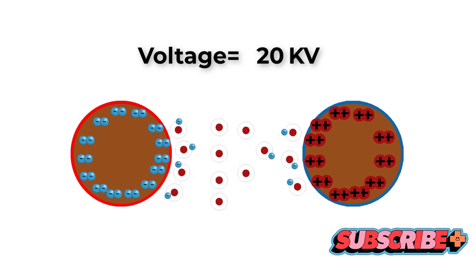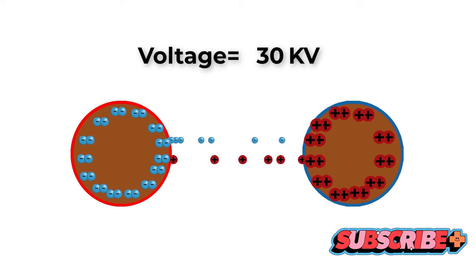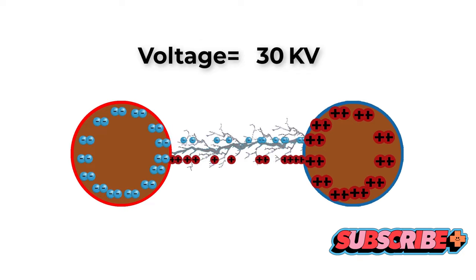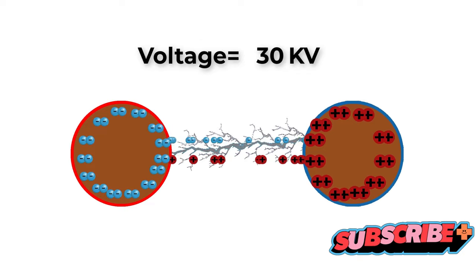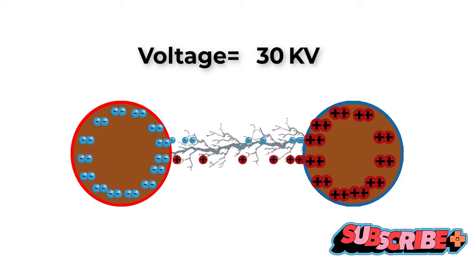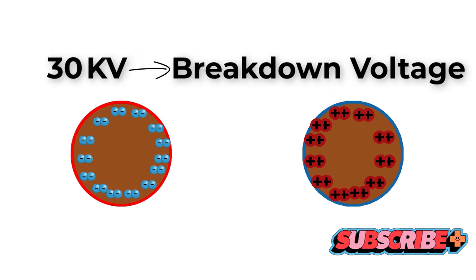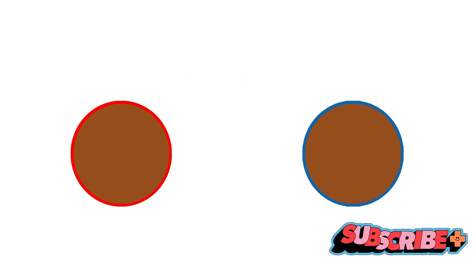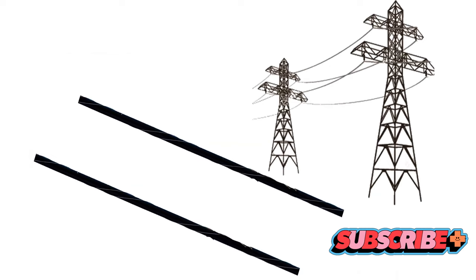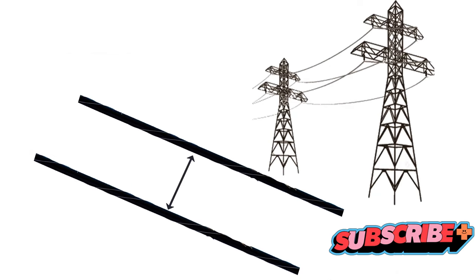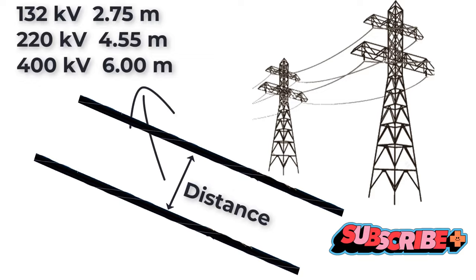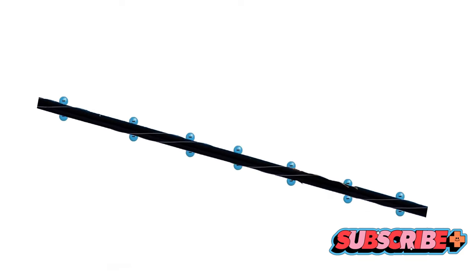Corona discharge is primarily caused by the ionization of air near conductors when the electric field strength surpasses a critical value. When the electric field gets too strong, it can rip electrons off of air molecules, creating a glowing region of ionized air, or corona. The size and shape of the conductors can also influence corona discharge — smaller and sharper conductors can intensify the electric field and increase the chances of corona discharge. The condition of the conductor's surface is another factor; a rough surface can create more points for the electric field to concentrate, leading to more corona.